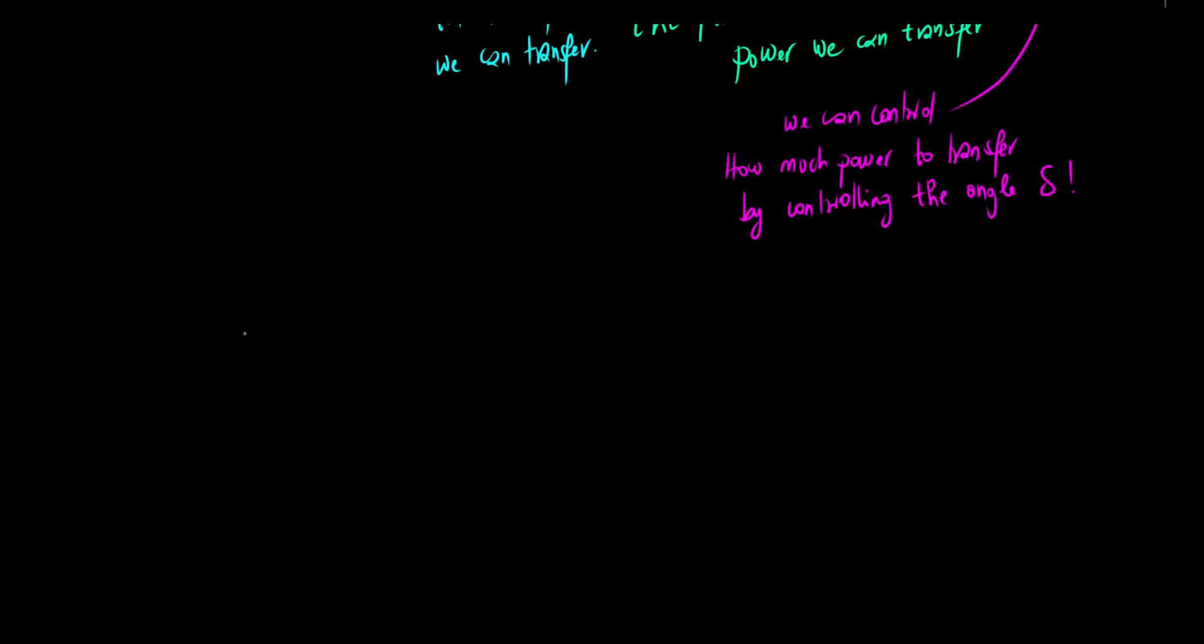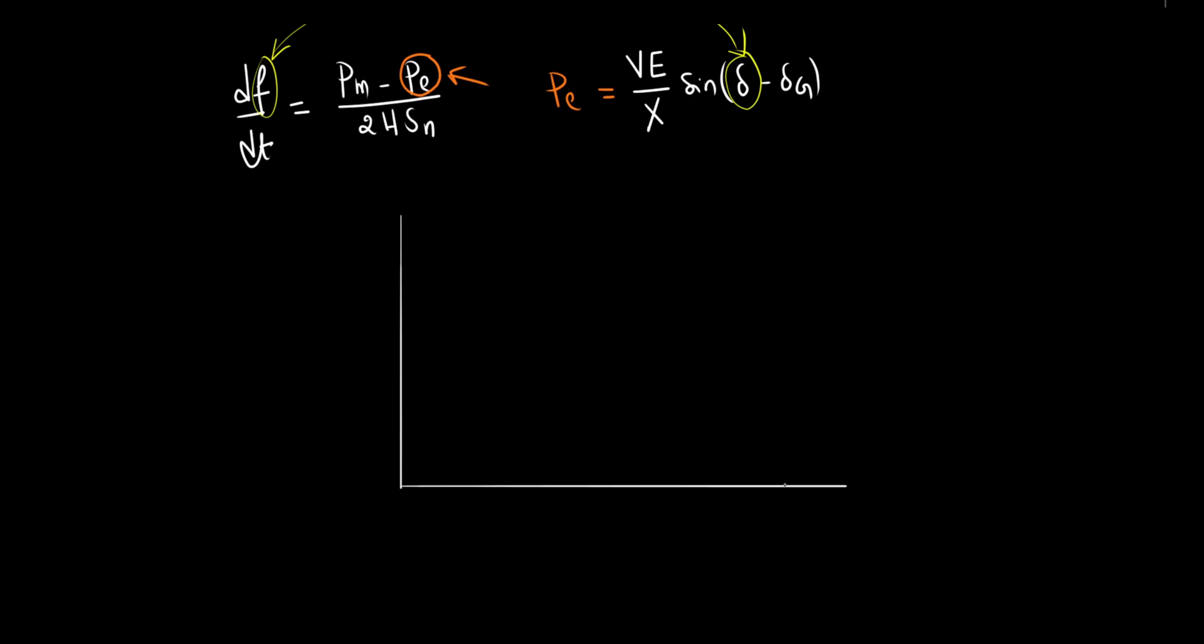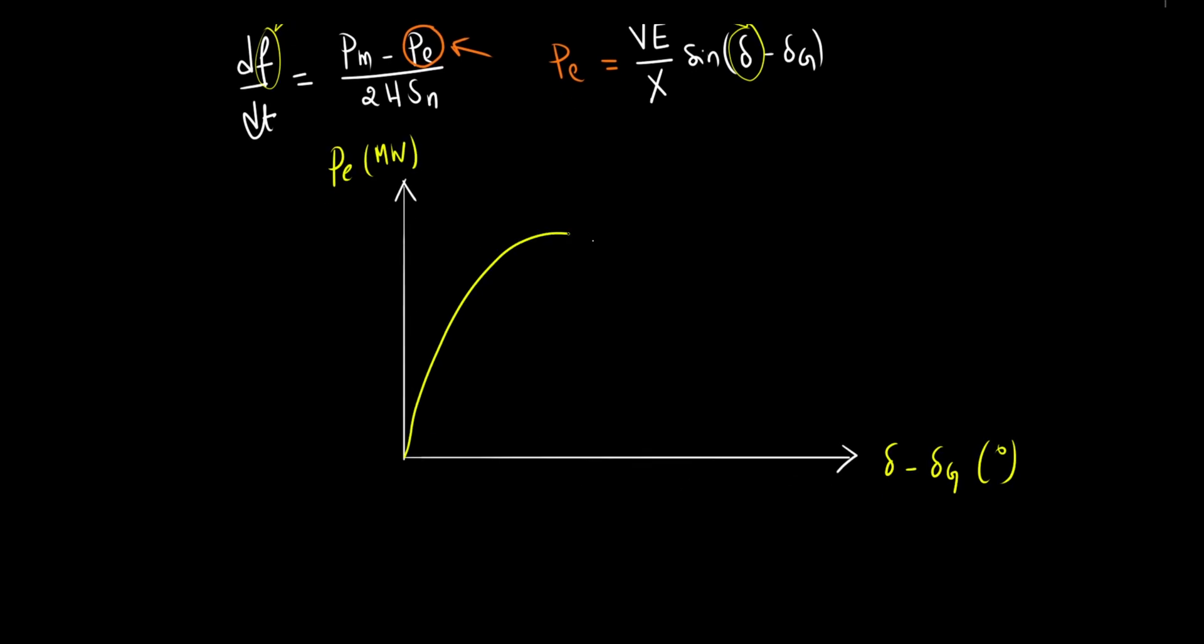Let me clarify the link between the swing equation and our power transfer equation. The electrical power in the swing equation can directly be replaced by our newly derived power transfer formula. Frequency, representing rotor speed, directly relates to the angular velocity of the rotor. Plotting power versus power angle gives us a familiar sinusoidal shape, peaking at 90 degrees, our maximum transferable power, called the pull-out power.